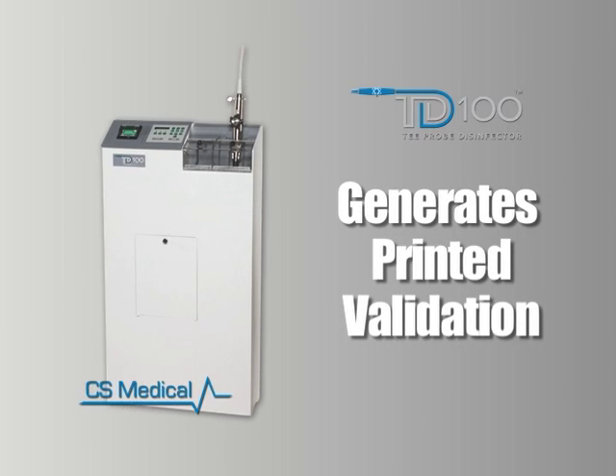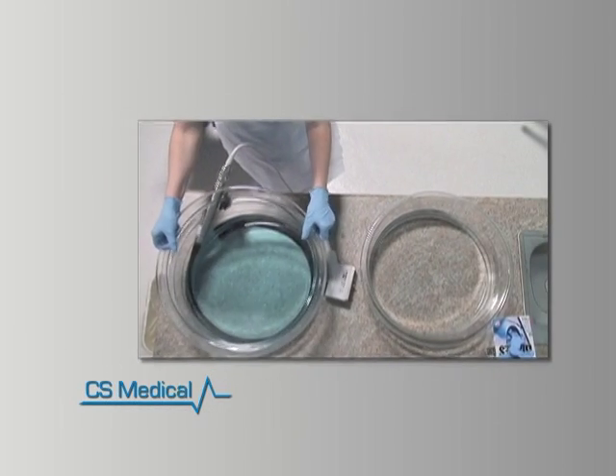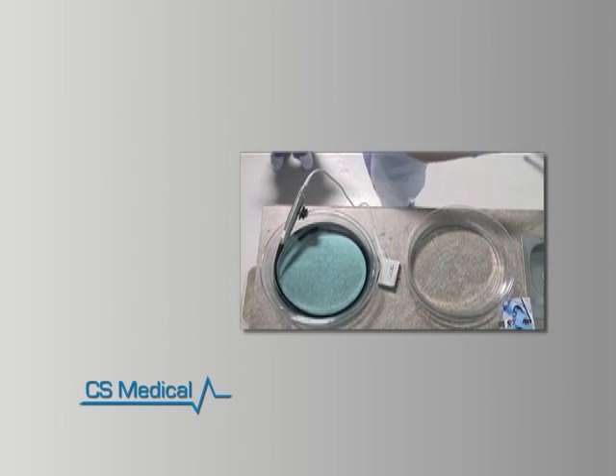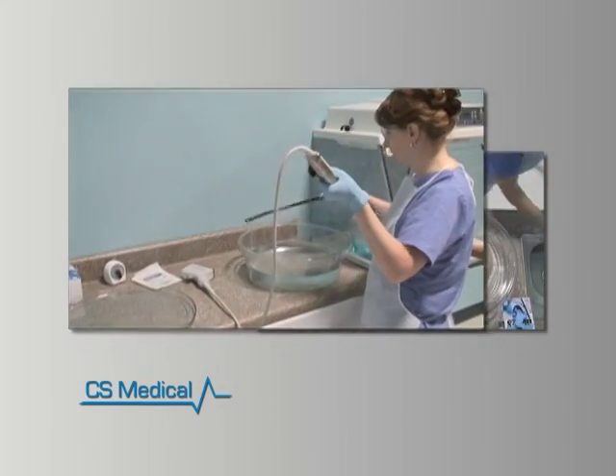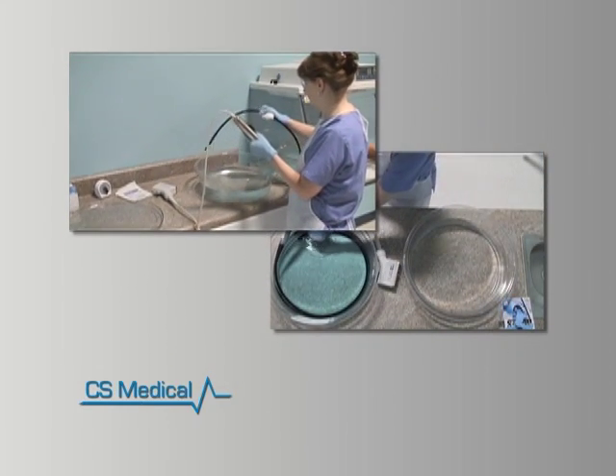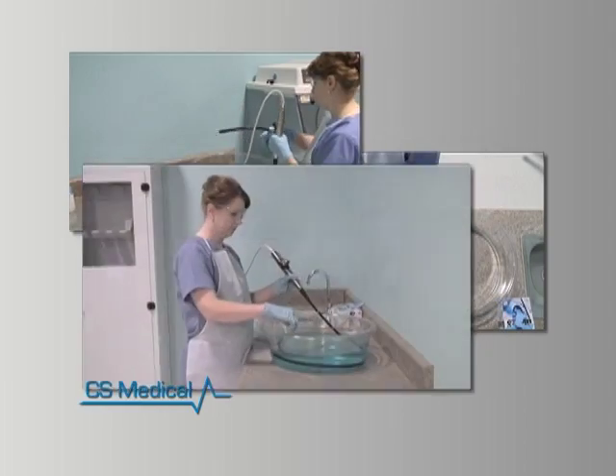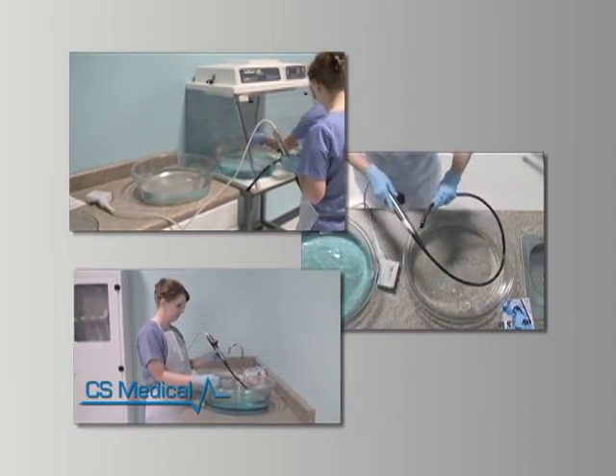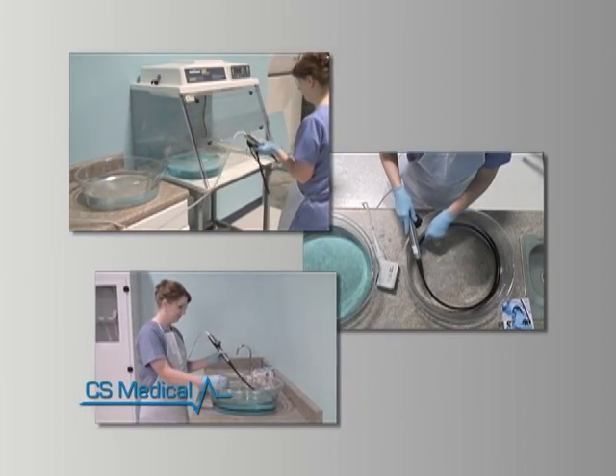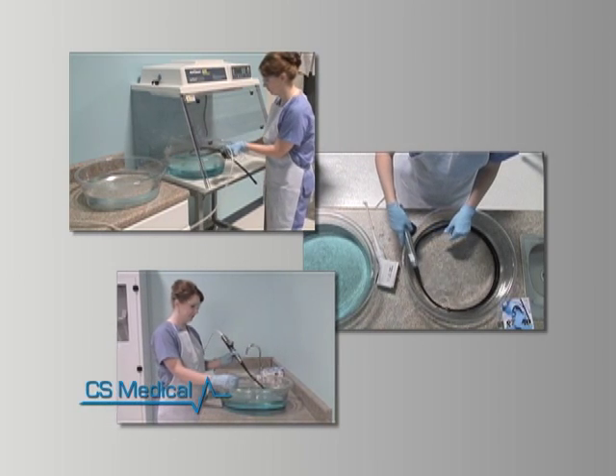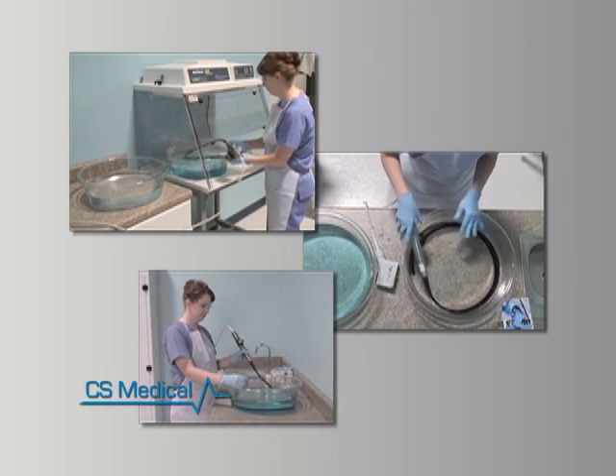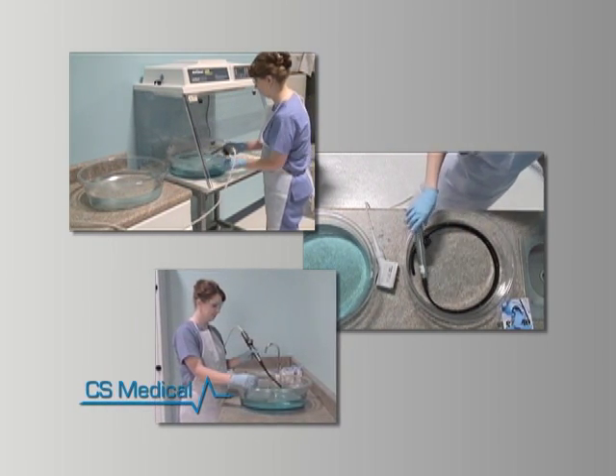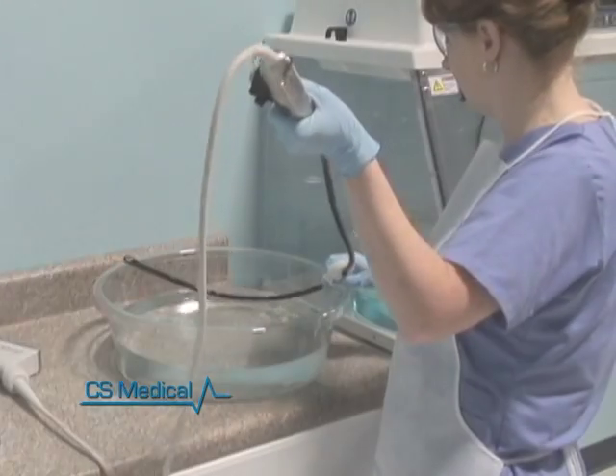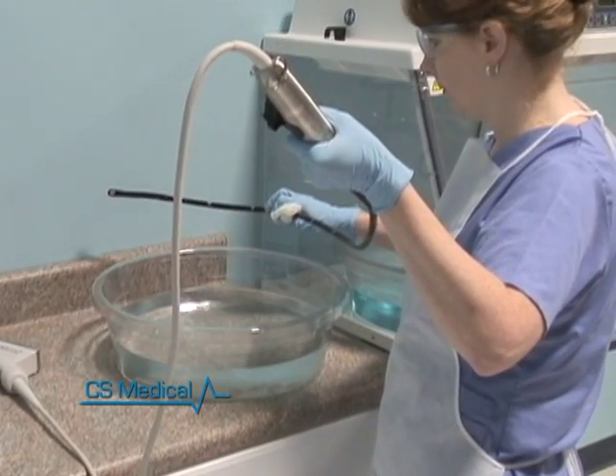the completed disinfectant cycle. Unlike endoscopes, transesophageal ultrasound probes cannot be submerged and therefore must be manually disinfected and rinsed. TEE probes are very sensitive and can be damaged if not cared for properly. Let's take a few minutes to review the current choices for manual reprocessing of your TEE probe. First, following probe manufacturer guidelines, you must pre-clean the probe.